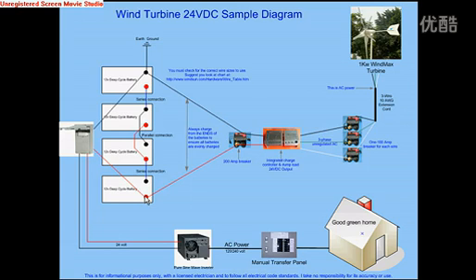So notice that now we have 24 volts from here to here, and 24 volts from here to here. What we want to do is increase the capacity of the system by having the 2 banks connected in parallel, which gives us double the capacity. So we go into a parallel connection, from the negative of one bank to the negative of the other bank, and the positive of one bank to the positive of the other bank. Now we have 2 banks of 24 volts connected in parallel.